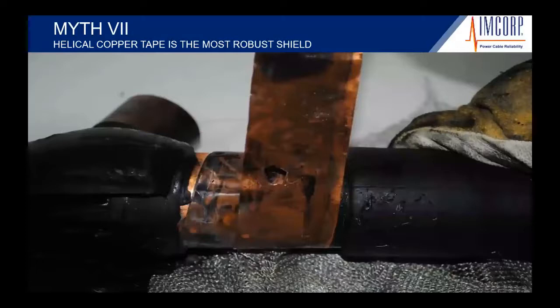Here's another area where the copper tape shield is beginning to erode. It's causing some pitting action. It's completely gone. Once this copper tape shield is completely gone, obviously you can have a floating ground, which can cause its own issues. But this is some of the things that we see in the field with this.